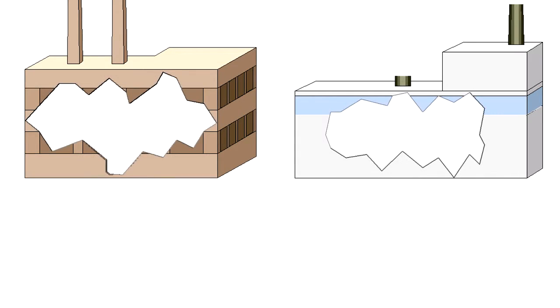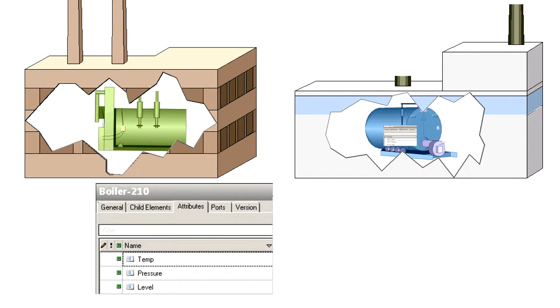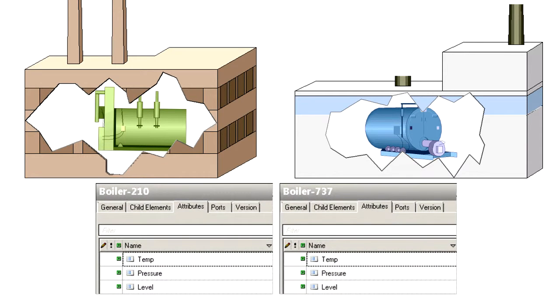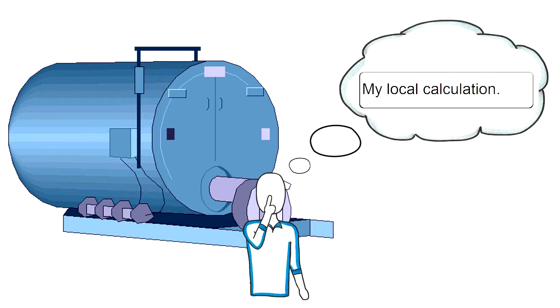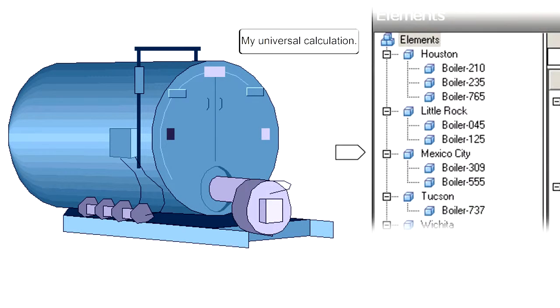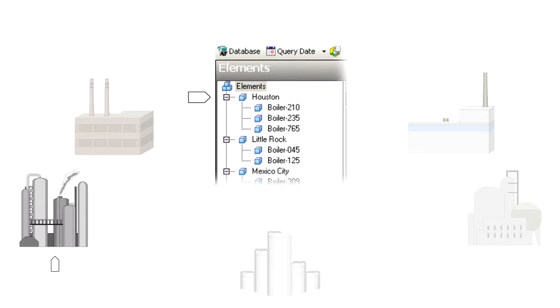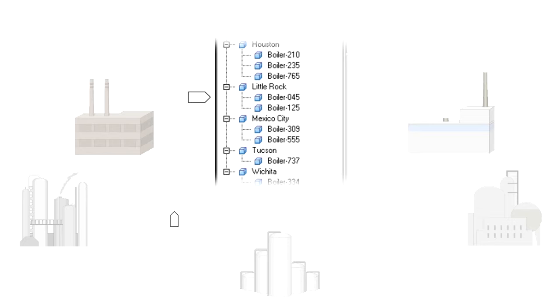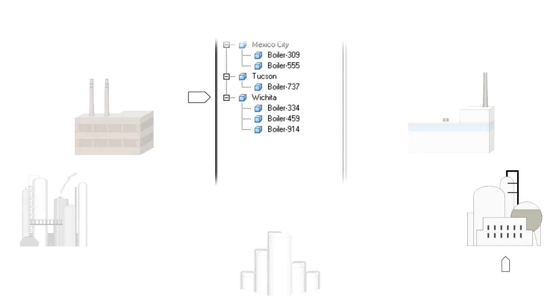The model used templates to make things consistent, so that each similar asset exposed the same set of sensors for trending, used the same names, and the same units of measure. Calculations and notifications that had been developed in isolation were now centrally defined with a template, and then applied to each asset that required them. In short, Jason and his colleagues learned how to use PI Asset Framework to apply a consistency that was required to share their data across the enterprise.